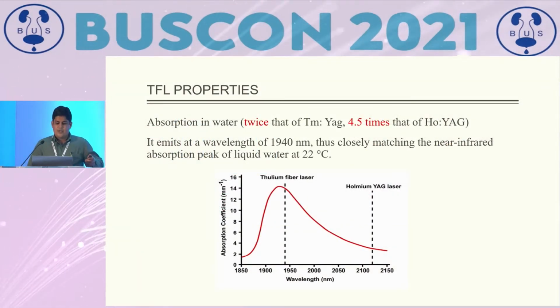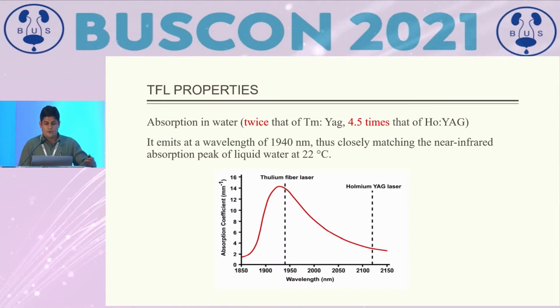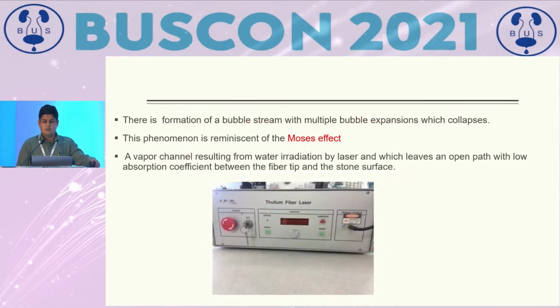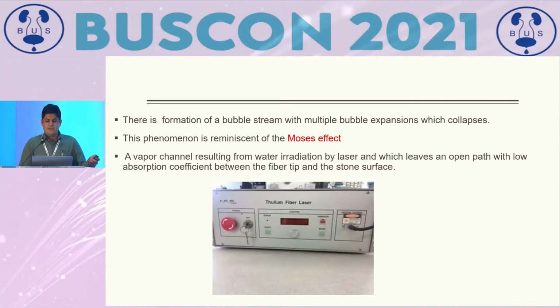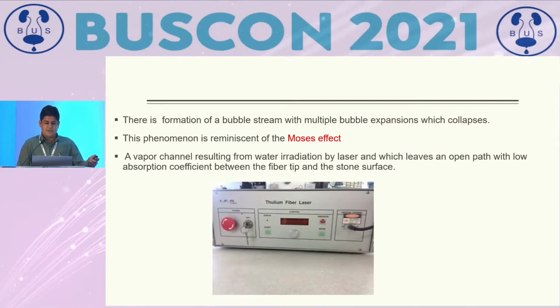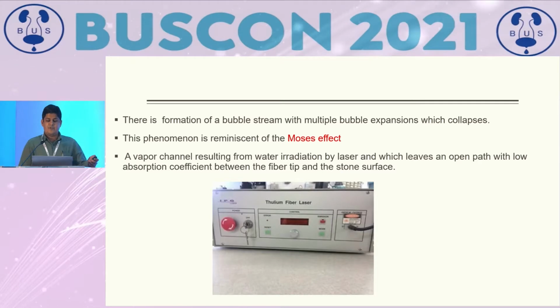Now, TFL absorption in water is 4.5 times that of Ho:YAG and emits a wavelength of 1940, thus closely matching the near infrared absorption peak of liquid water at 22 degrees centigrade. There is a formation of bubble stream with multiple bubble expansion which collapses. This phenomenon is reminiscent of the Moses effect, a vapor channel resulting from water irradiation by laser and which leaves an open path with low absorption coefficient between fiber tip and stone surface, which is very well explained in the next video. Please play the video.